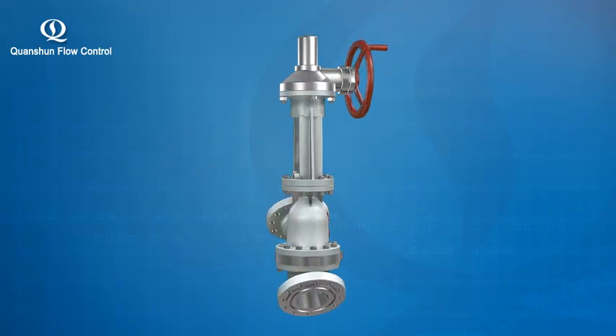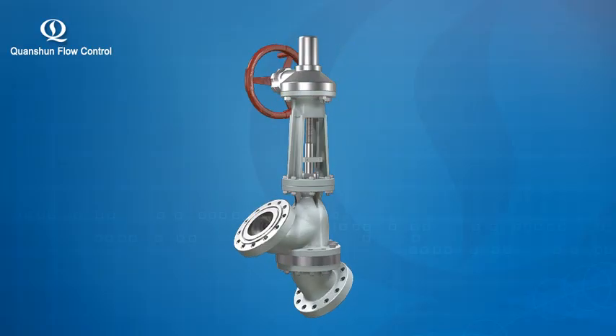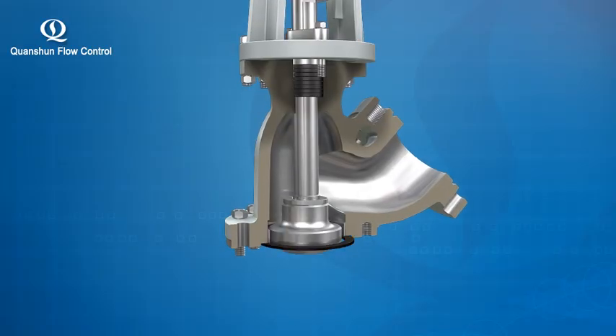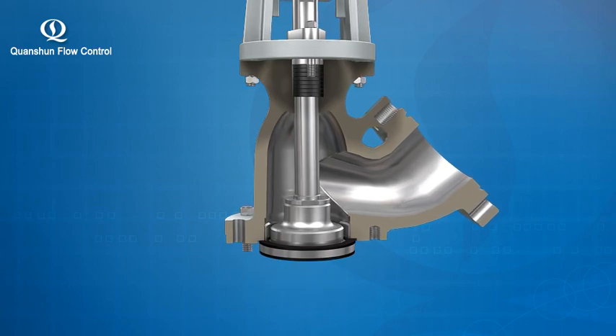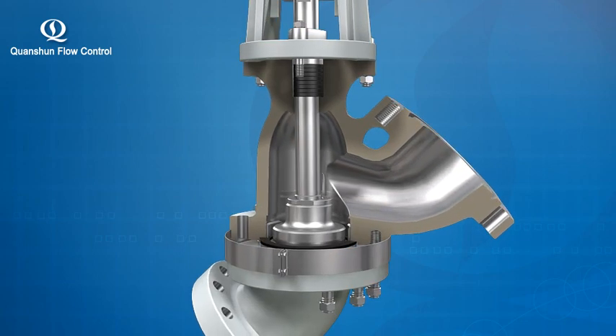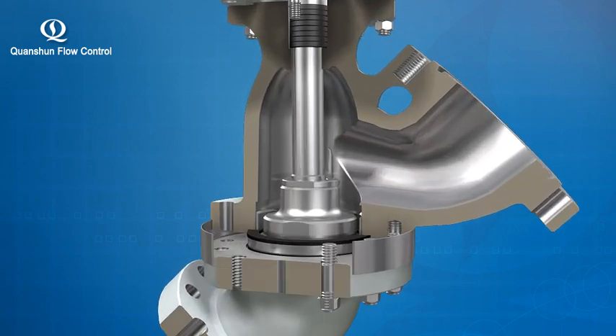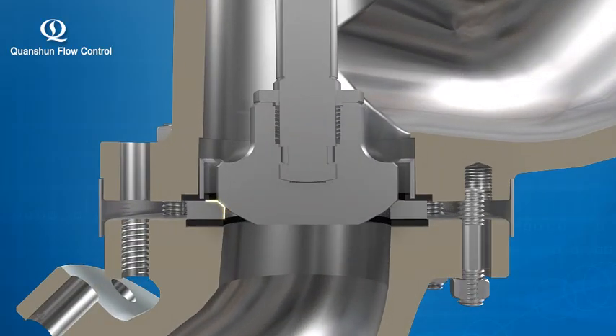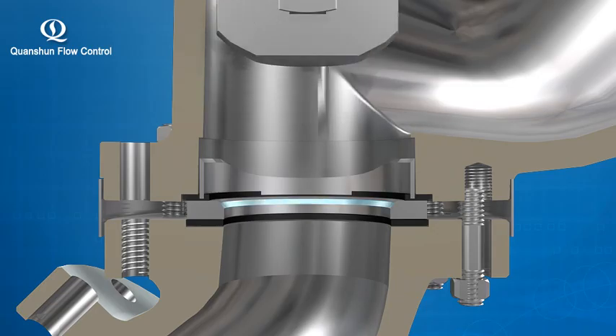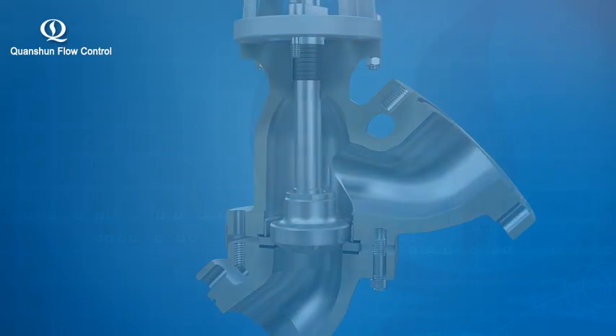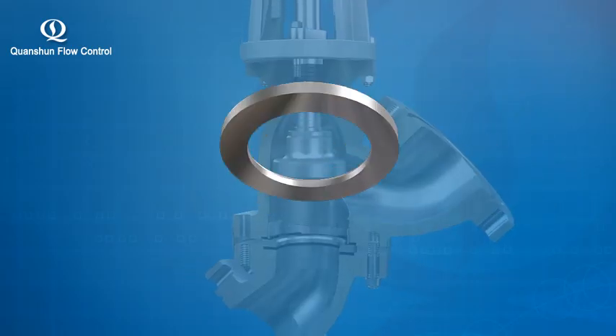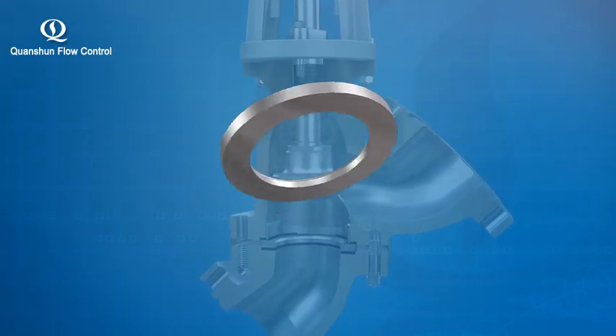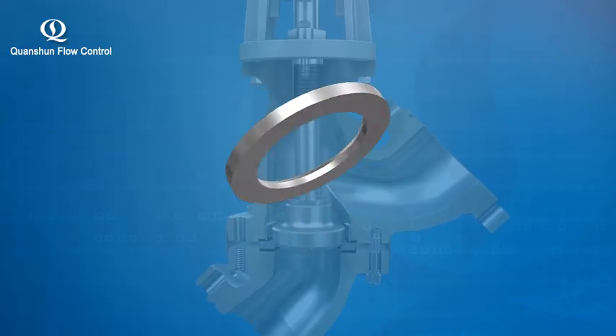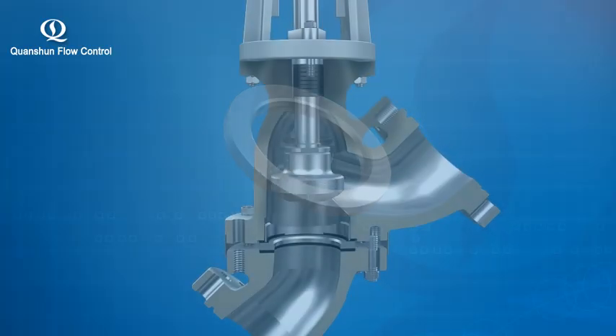3. The design of separated seat and body. The seat is kept centering relative to the stem and disc during assembly to achieve tight cutoff in the long run. The separated valve seat guarantees a uniform thickness of the weld deposit and the desired hardness after heat treatment in case of special alloy materials servicing, making it easy to conduct non-destructive tests on the seal face and for instant inspection and repair by removing the valve body connecting bolts.